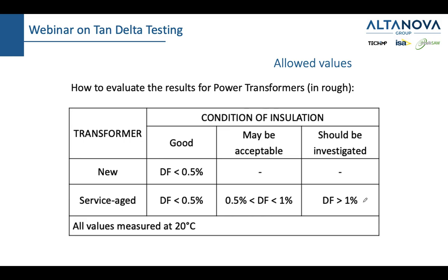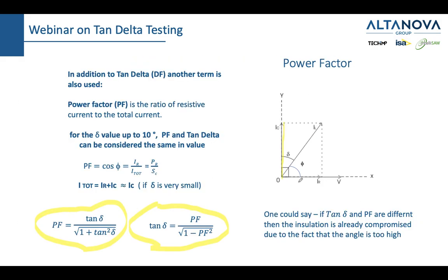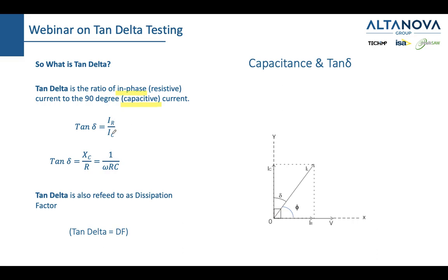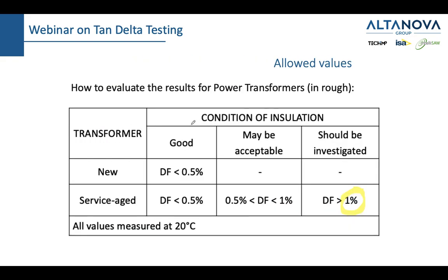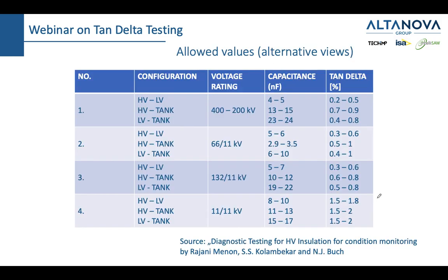So what I'm saying here is that maybe you have noticed that all of a sudden I've started using percentages. Well, I'm using percentages simply because when you measure a tan delta, you have two values which are both amps. So you get a number which has no dimension. But that number is usually 0.01 or 0.05 or 0.005. So instead of saying 0.00, you just multiply that number by 100 and then you slap the percentage sign onto it and express yourself in percentage. So long story short, tan delta should be less than 1%. So this is what we talk about when we talk about transformers.